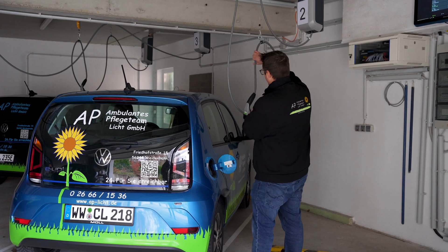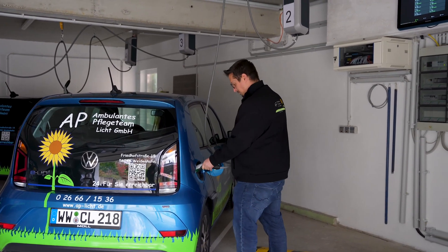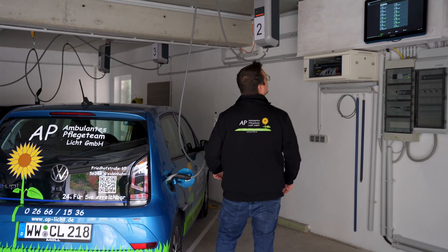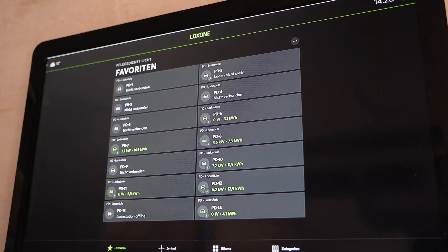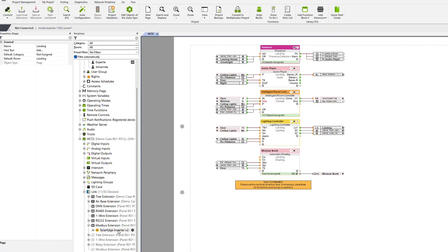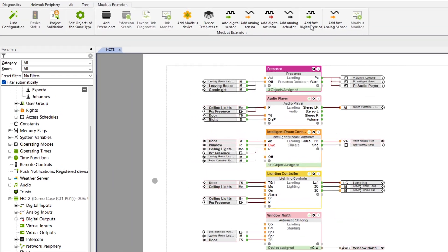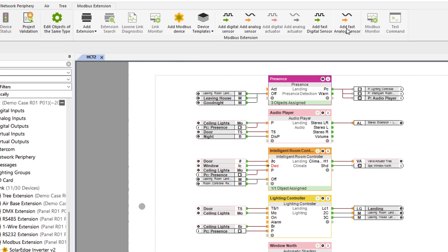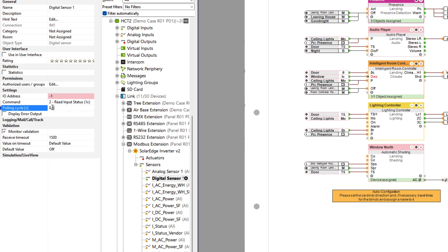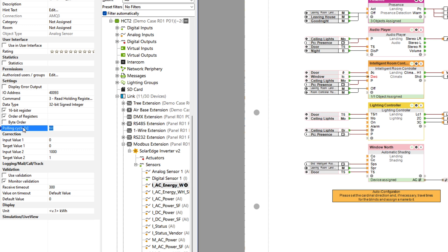Modern energy management involves the requirement to react very quickly to changes in performance in order to avoid load peaks. For example, an electric car charging park where several wallboxes are in operation at the same time requires a quick reaction in order not to exceed maximum performance. Thanks to the new Modbus high performance inputs, it is now possible to set a minimum query interval of up to 0.1 seconds with 2 Modbus inputs per device. The minimum query interval has been reduced from 5 seconds to 1 second. The air products Modbus Air and the wallbox Air are excluded from this feature.